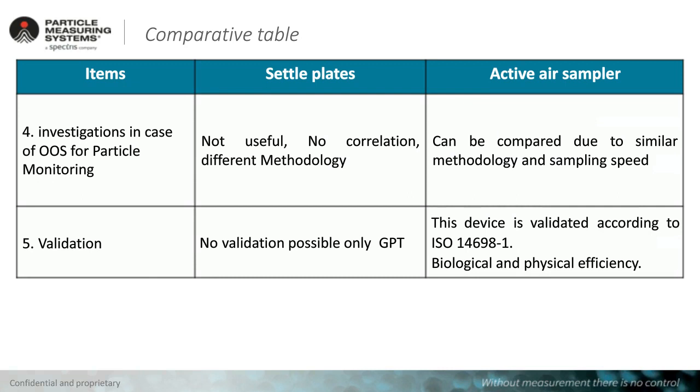The last point, which is really, I would say, the most important point after all, is the fact that validation of settle plates is almost impossible. The only thing you can do is a growth promotion test that shows that microorganisms would have grown on the surface.